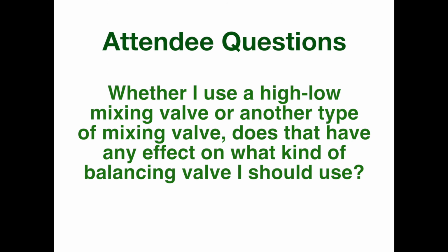But if you're just doing a single loop, the balancing valve that Cody showed earlier is a good one, because you can make really fine adjustments on it and dial in that flow, so you avoid that temperature creep issue. So it really depends on the application on which valve you would select, but certainly look at our ThermoSetter or the 116 valve for big complicated piping, recirc piping projects.